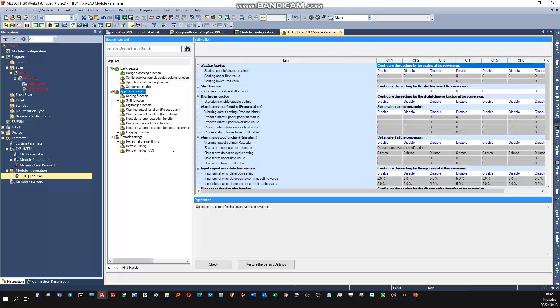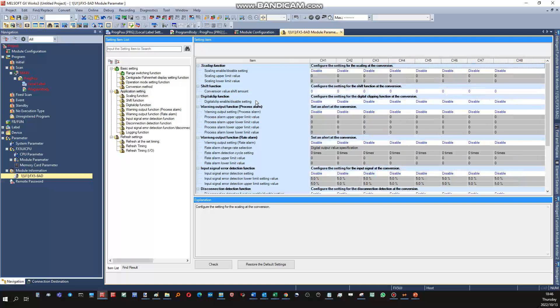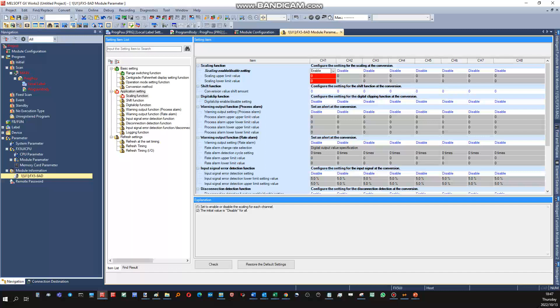Looking at the application settings here, you can do the scaling of each channel within the PLC without writing a PLC program or using an HMI or SCADA. You can enable it here and then add the upper and lower limits in your engineering value range — for example, 0 to 2000 kPa, 0 to 10 bar, 120 to 3000 degrees Celsius, or minus 50 to 120 degrees Celsius. However, we won't be looking at scaling in this example, so I'm going to disable that part.